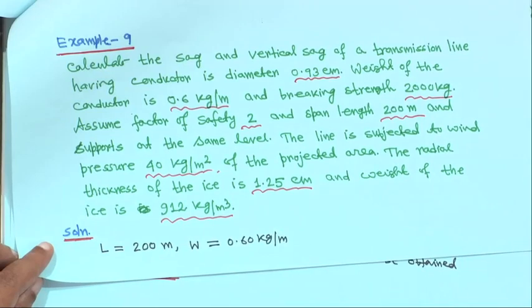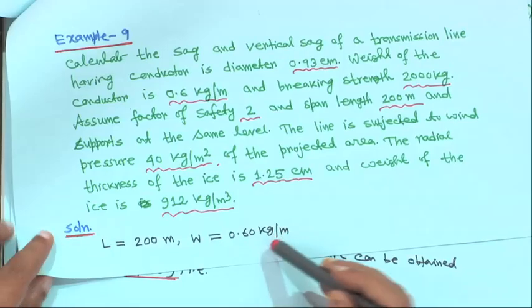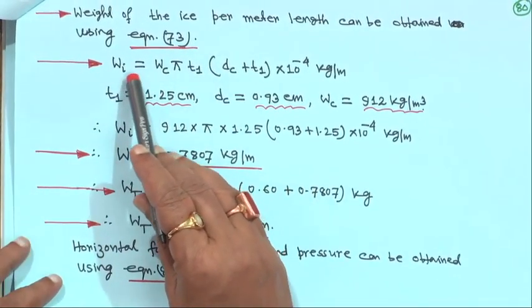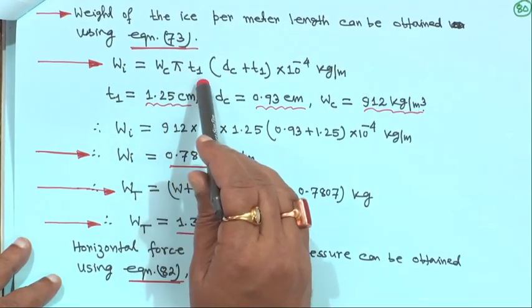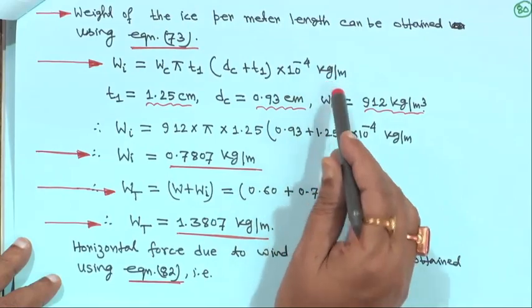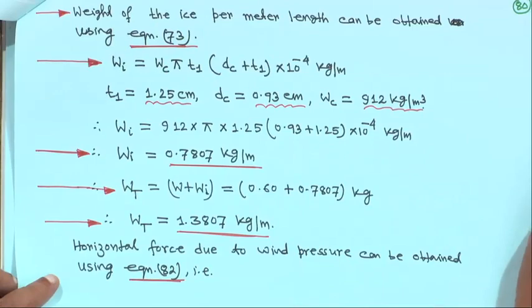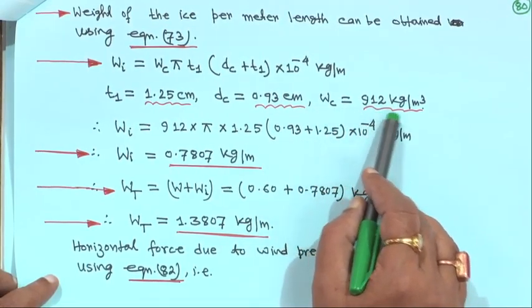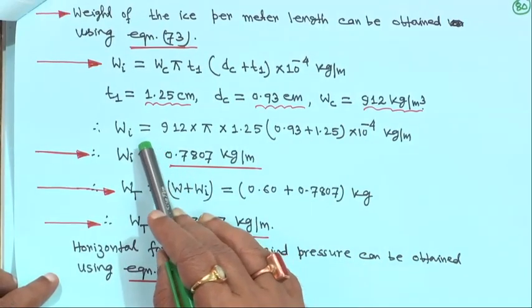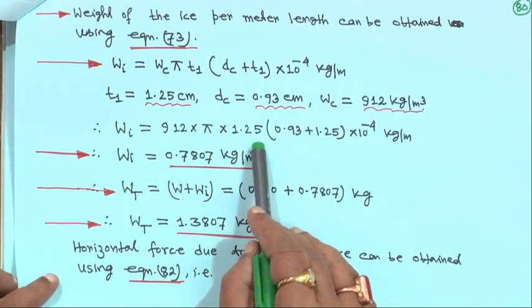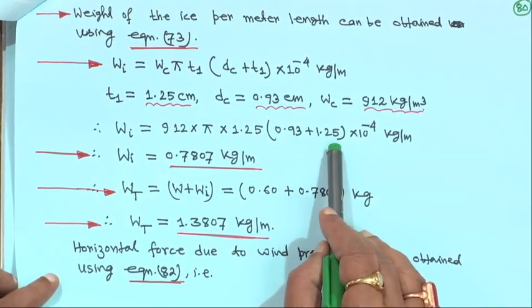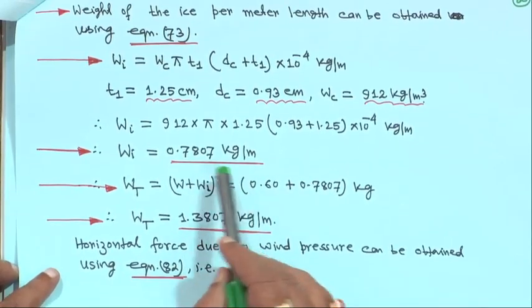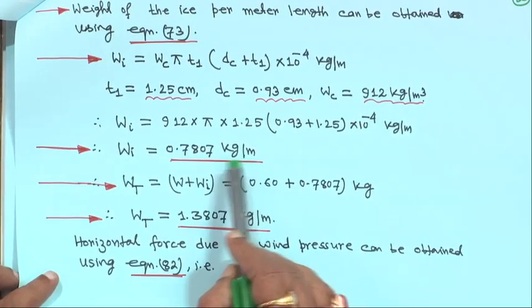L is 200 meter and W is 0.6 kg per meter. Weight of ice per meter length using equation 73: Wi is equal to Wc·pi·T1·(DC plus T1) into 10 to the power minus 4 kg per meter. T1 is 1.25 centimeter, DC is 0.93 centimeter, and Wc is 912 kg per meter cube. Substituting: Wi equals 912 into pi into 1.25 into (0.93 plus 1.25) into 10 to the power minus 4, giving Wi equal to 0.7807 kg per meter.